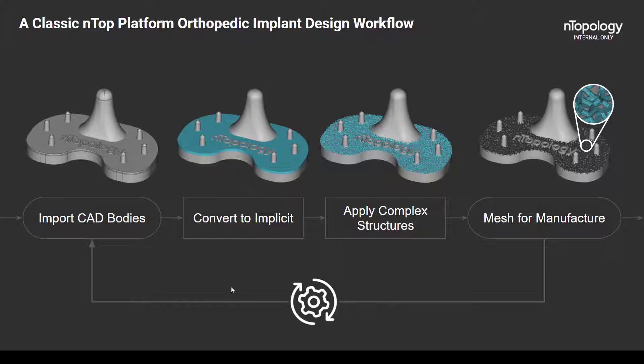So, typically, the main form and net shape of your implant design is created in your traditional CAD tool, and each part configuration is exported as a separate multibody parasolid file. What that means is that if you have 87 part configurations in your part family, you should be exporting out 87 multibody parasolids to work with. This may seem a bit cumbersome at first, but it's actually one of the most thorough approaches to ensure the highest level of traceability when you're working through the entire part family.